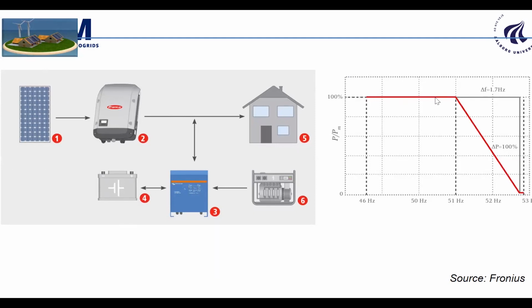You can see here that we have a very similar curve. Once we surpass this threshold, in that case 51 Hertz, the MPPT curve goes out. You can regulate this curve according to your grid code, which will tell you how to do it, or if it's a microgrid system, you have to adapt these frequency ranges.